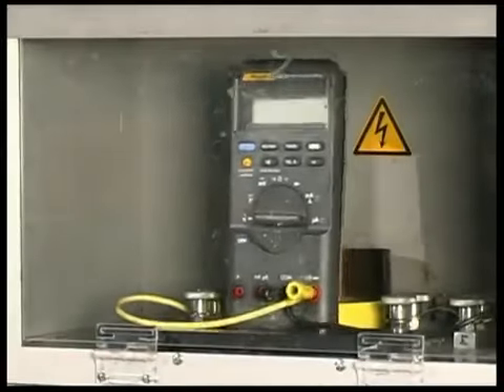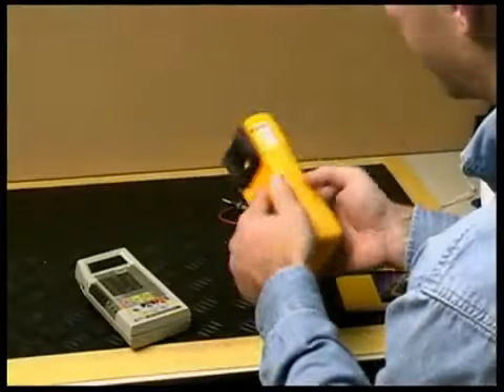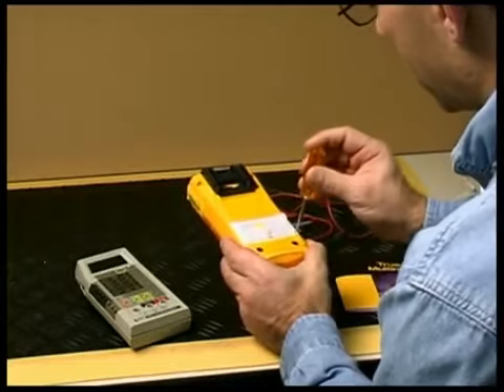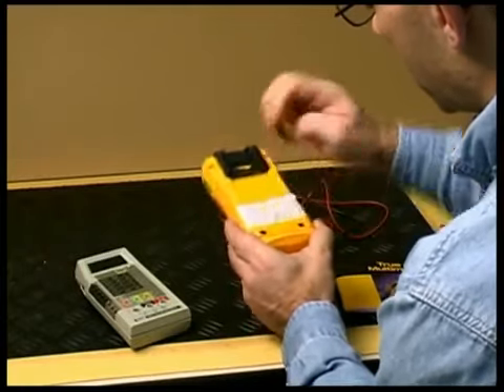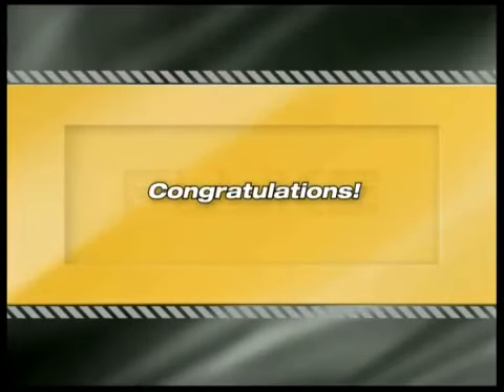Finally, if you've had a blown fuse or mishap with your tester, make sure you get it checked out and calibrated before using it in a high-energy environment. If your test instrument passes these tests, congratulations! You are successfully managing some of the risks inherent in measuring electrical equipment.